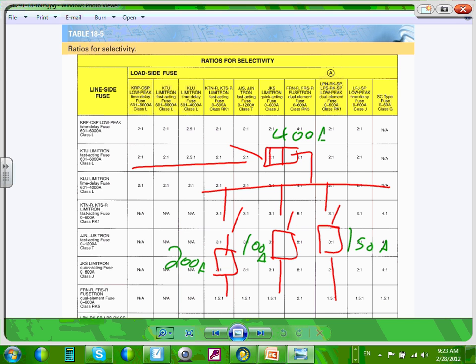Now here's where you can get into issues. Again, rule of thumb. Take this. What if I have a fuse here, and this fuse was 300 amp? Now a 300 amp fed from a 400 amp, you might not be able to coordinate these babies. So here's a rule of thumb. Whatever your main is, don't make your largest feeder higher than half of the main. Your main is 1000 amp, the largest feeder is no more than 500 amp. Your main is 4000 amp, the largest feeder out of the 4000 amp is no more than what? 2000 amp. Does that make sense?